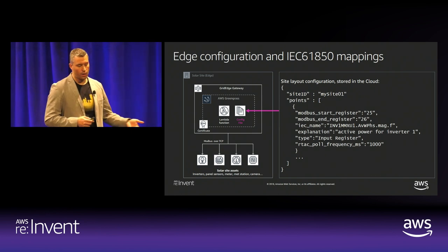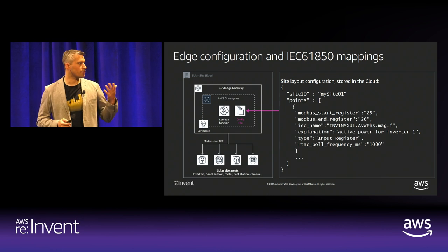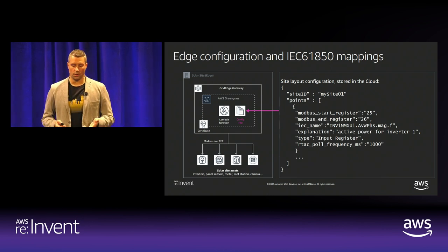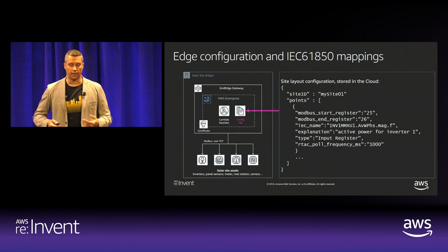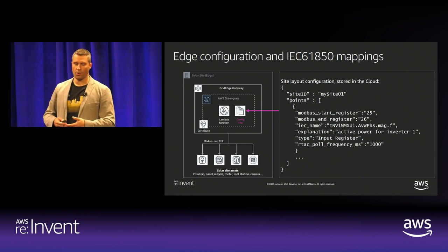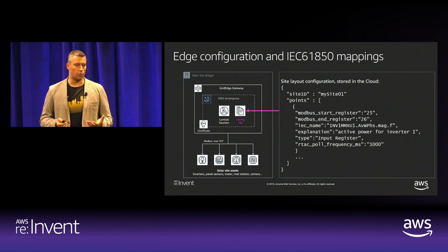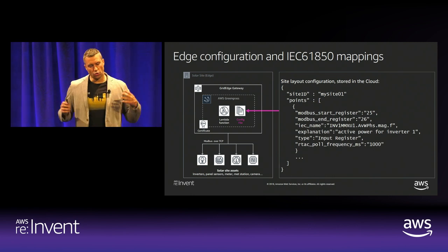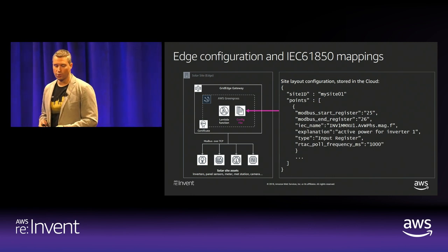If we're looking for power or temperature, those might be different. But for temperature, for example, in degrees Celsius, you might want to specify that this value should never be, I don't know, below minus 50 Celsius and above 120 Celsius or something like that. Anything out of that range shouldn't really be considered. And it's probably a false reading, or you have a serious problem.